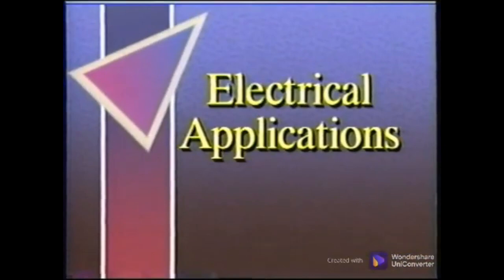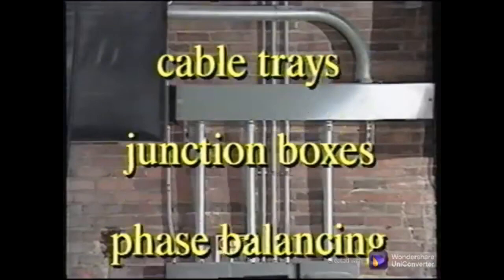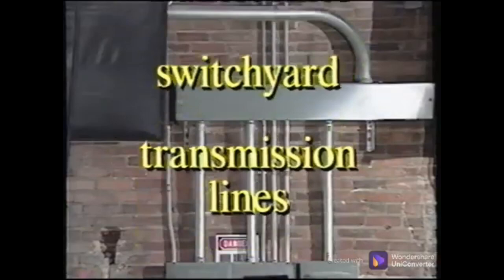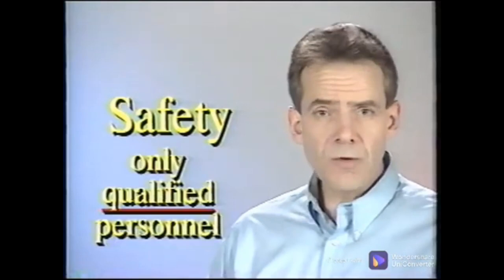Thermography in industry today is most often used for detecting electrical anomalies. Common applications include electrical panels, splices, cable trays, junction boxes, phase balancing, overloading, as well as transformers, switchyards, and even transmission lines. The first and major consideration when scanning electrical equipment is safety. Always use extreme caution and make sure the personnel with you are qualified and familiar with the equipment to be surveyed.